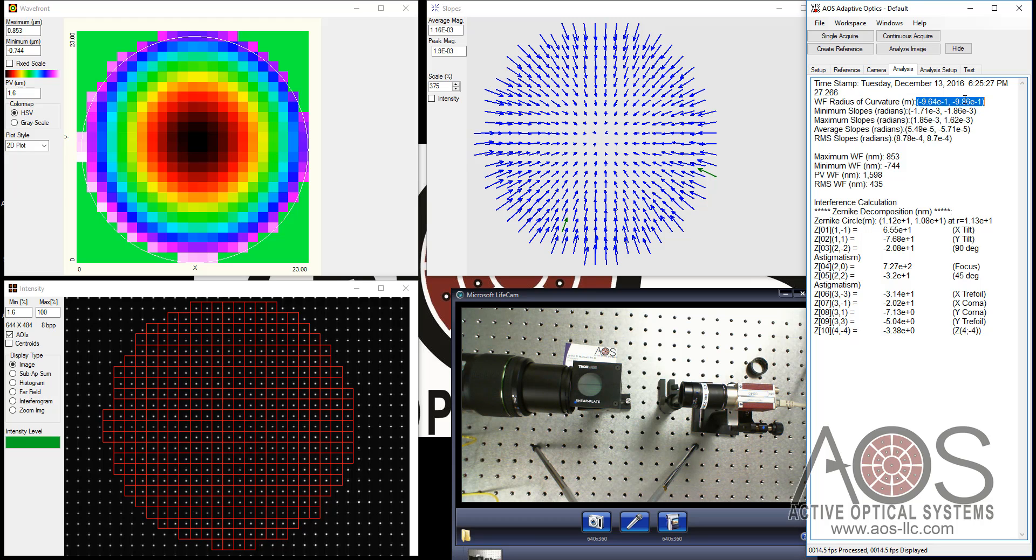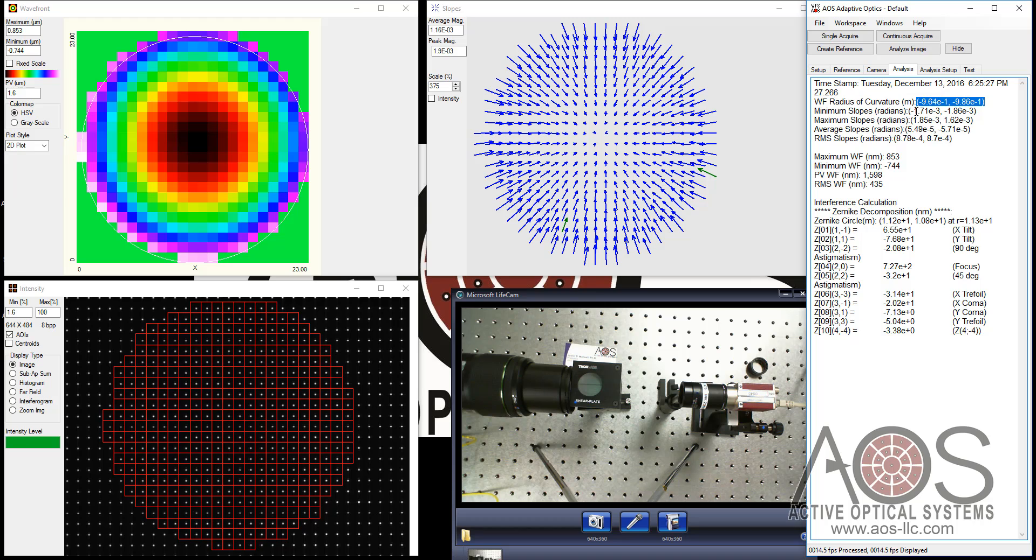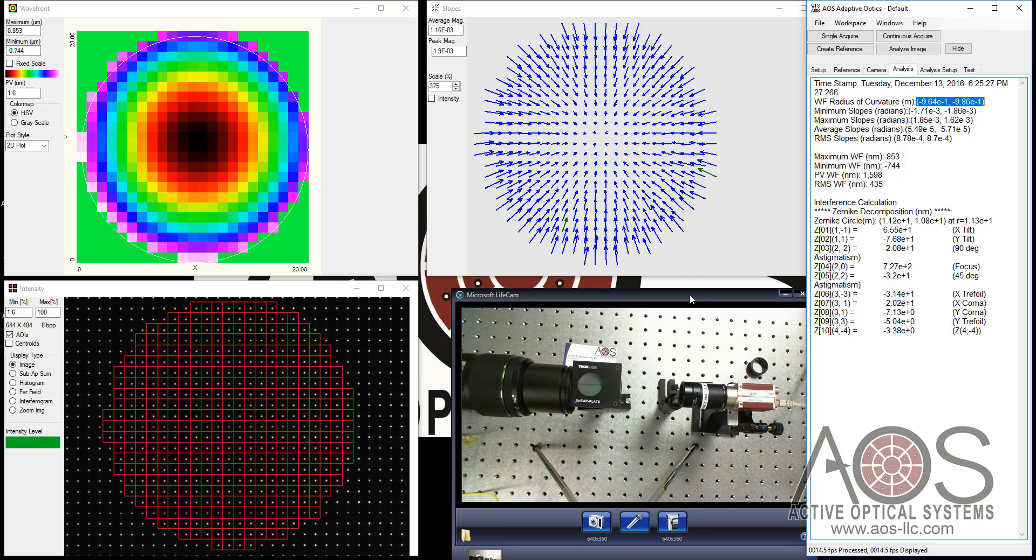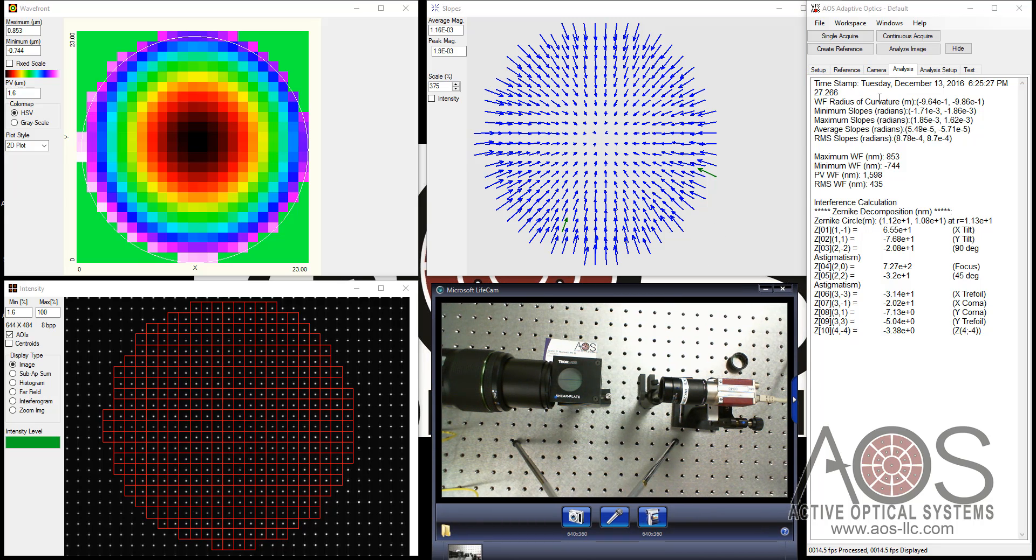So we're seeing a curvature that is consistent with this being a one meter focal length lens. Because again, we have about that 40 millimeter separation between the lens and the lens array. There's a little bit of a difference here, and this could be any of a number of things. It could be a defect in the lens. It could be a slight misalignment in the optical system. For now, I would look at this and say, yep, I believe that this is about approximately a one meter focal length lens within the tolerances of the manufacturing probably for this part.